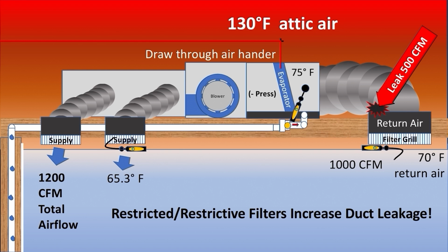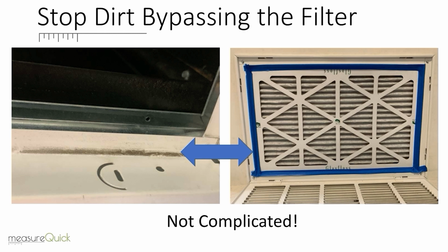You notice on there, we're showing those 2 Fieldpiece probes. We're on the inlet to the return air filter grill, and we're on the supply, first supply. So that one up there, I don't know if we put a little note on there, but we should have, where it says 75-degree air. But what we're showing there is basically we're testing from inlet to outlet of the system. Dirt bypassing the filter grill.